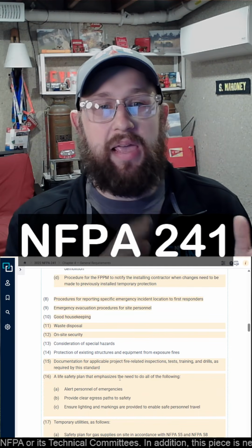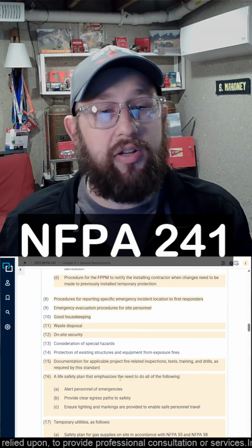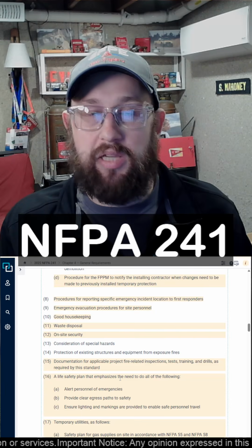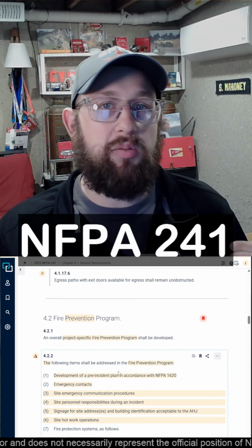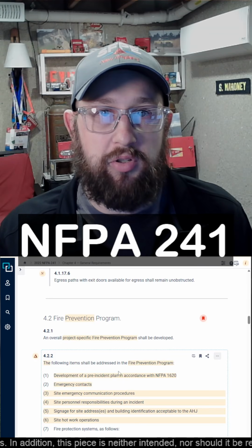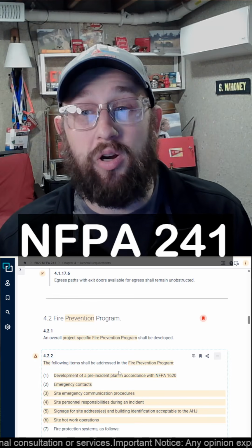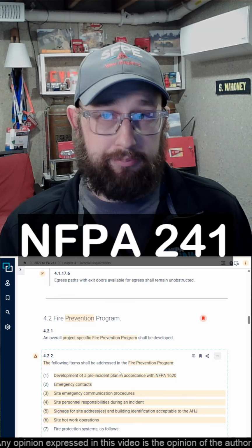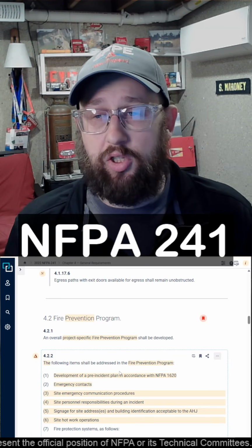As well as, do we have life safety plans in place for the workers and the people on the construction site? And what are our temporary utilities look like? So this plan gets written for this specific project based on those hazards. And it's written by a person who's knowledgeable. It needs to be approved by the authority having jurisdiction before construction starts. It's a very crucial part to safeguarding these construction sites.